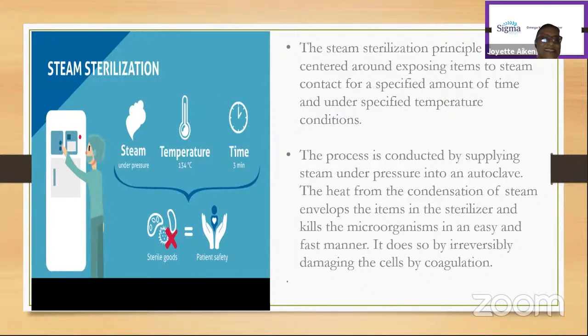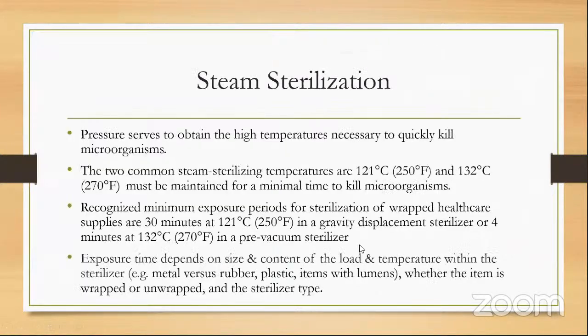Okay, so the principles of steam sterilization center around using steam under pressure, high temperature, and a specific time to achieve sterilization. The process is conducted by supplying steam under pressure into an autoclave. The heat from the condensation of steam envelops the item in the sterilizer and kills the microorganisms in an easy and fast manner. It does this by irreversibly damaging the cells by coagulation. The pressure in the autoclave helps to build up the high temperatures necessary to quickly kill the microorganisms.